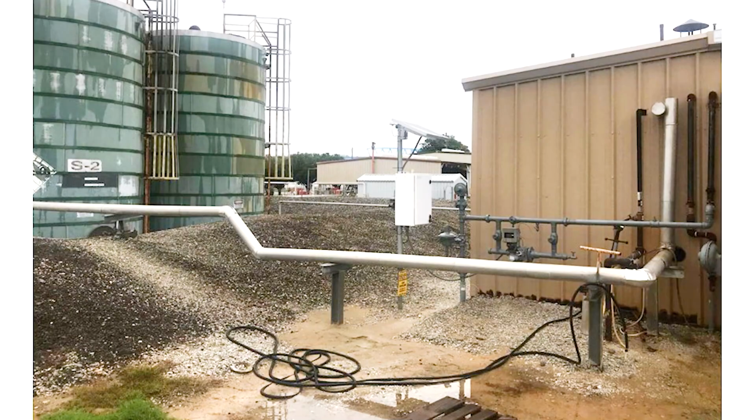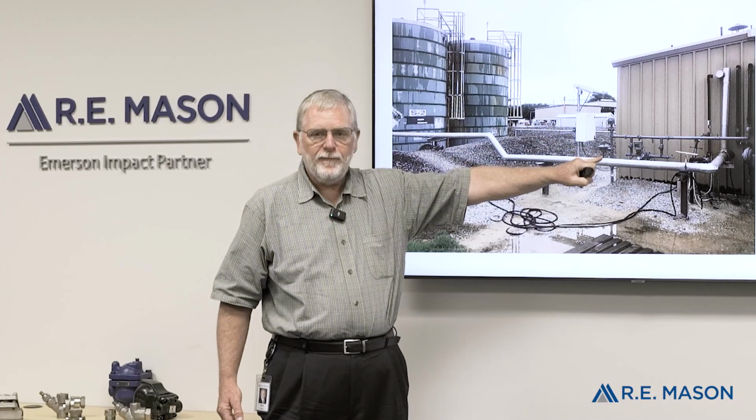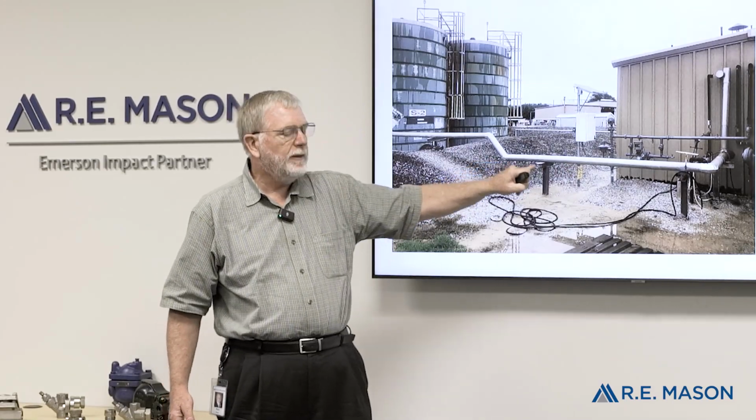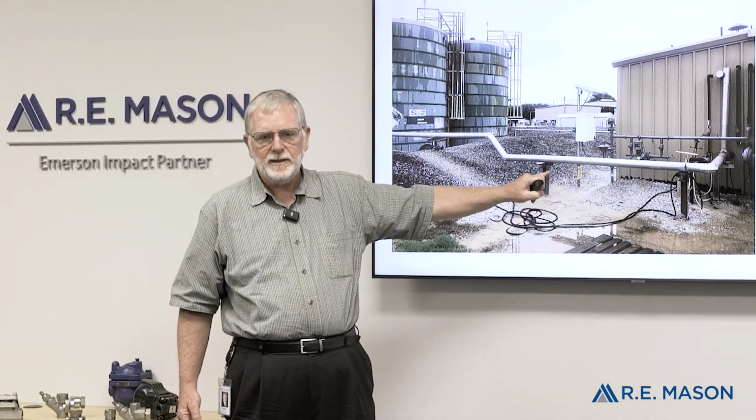The other thing in a steam system audit that's often overlooked when you're just having a steam trap survey done, one is being the fact that here you can see in the picture, you've got a low point in your piping from where the pipe falls coming out of the building over. That area right there collects condensate.